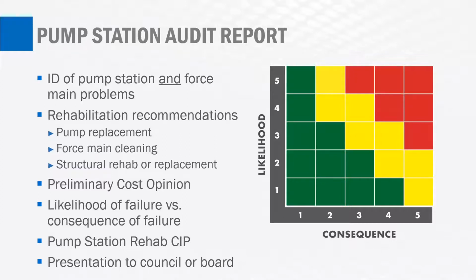So it's important to develop those rehab recommendations and then come up with a preliminary cost opinion for those rehab recommendations. Then what we need to do, as you can see in that graphic to the right, is look at the likelihood of failure versus the consequence of failure. The likelihood of failure is determined based on our overall assessment, what's happening out there. How's the pump performing? And that's all part of your assessment and coming up with that risk or likelihood of failure.